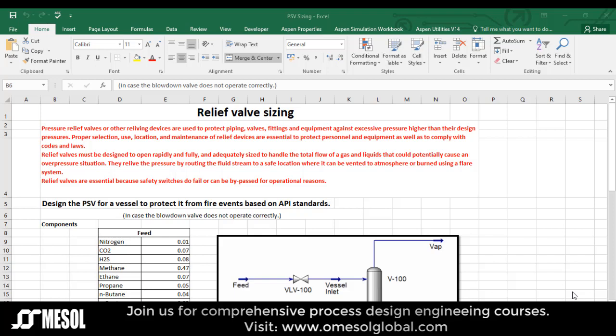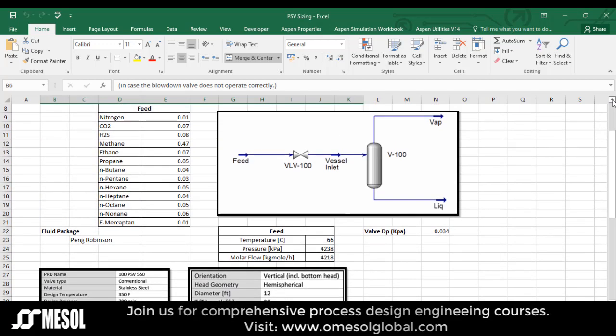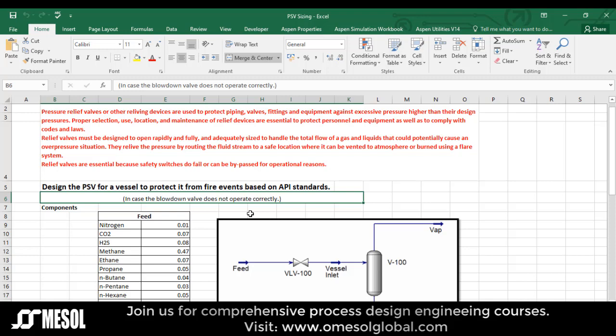Relief valves are essential because safety switches do fail or can be bypassed for operational reasons. So this is our flow sheet. We will try to design a PSV for a vessel to protect it from a fire event based on API standards.